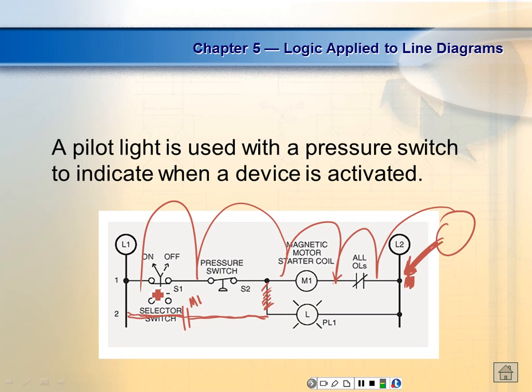So we just go up there with an alligator clip, find L2, find that wire number anywhere, right? You understand, because it's going to have the same number. If it was wire number 5, any terminal that's labeled 5 is L2. So just clip it on there and then start troubleshooting back.